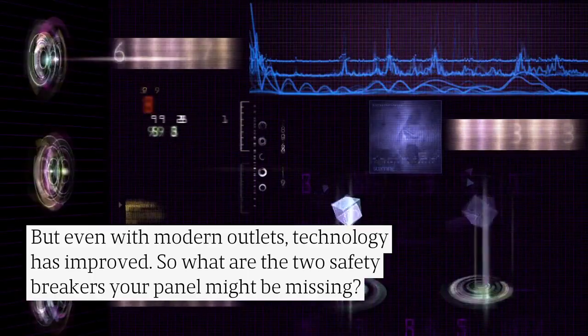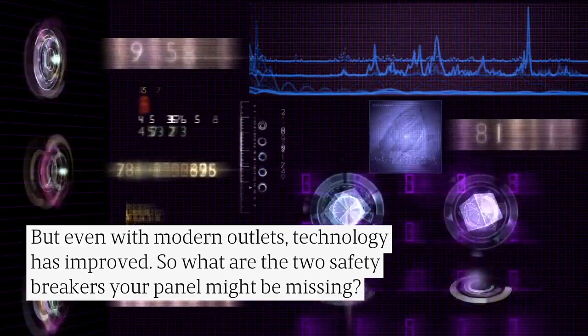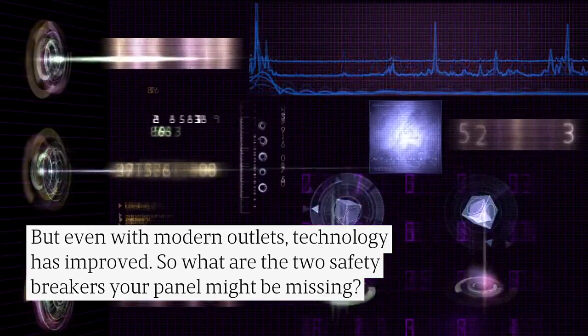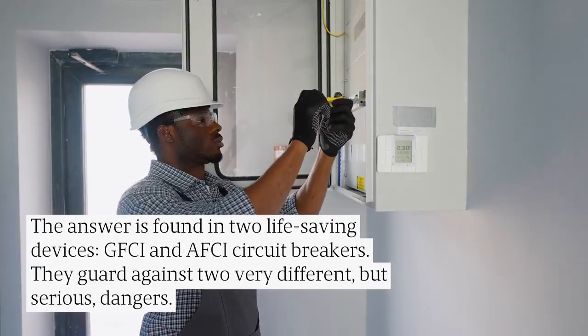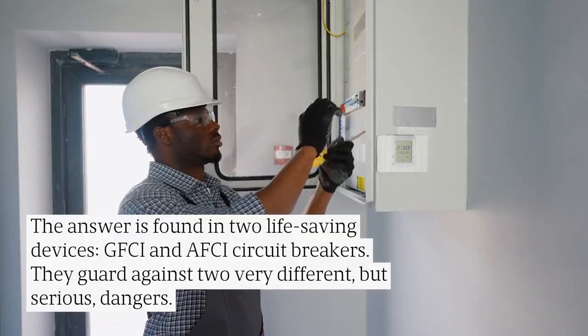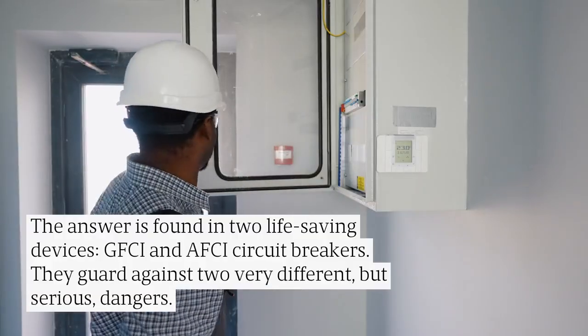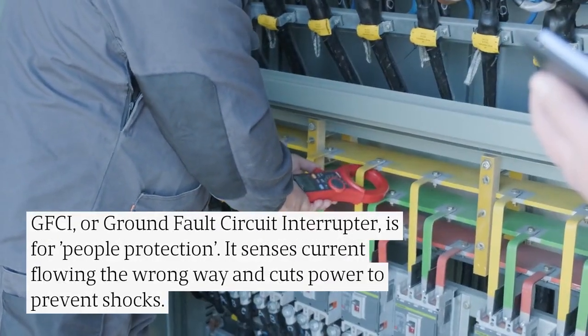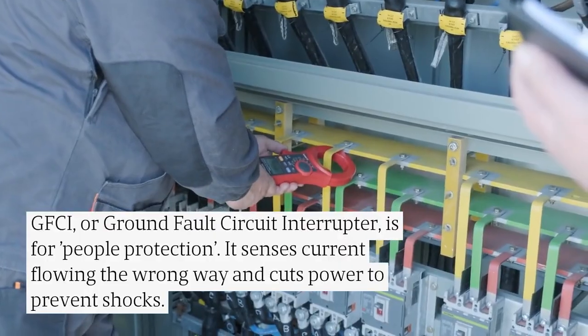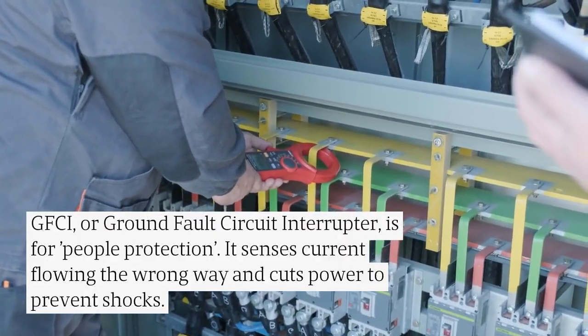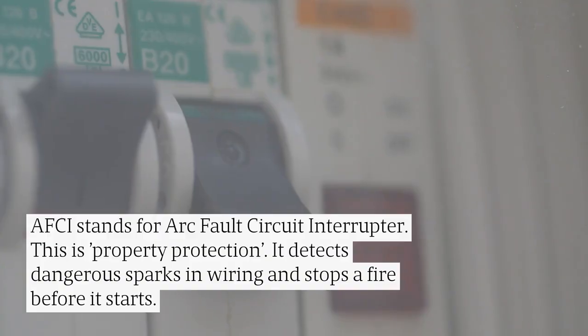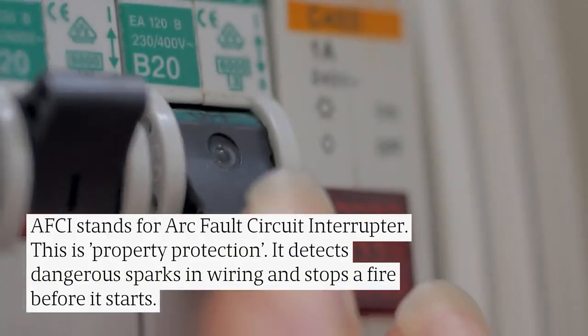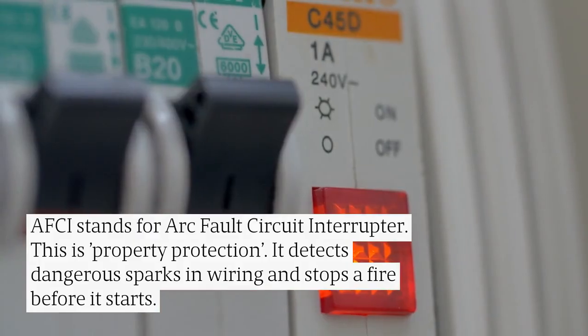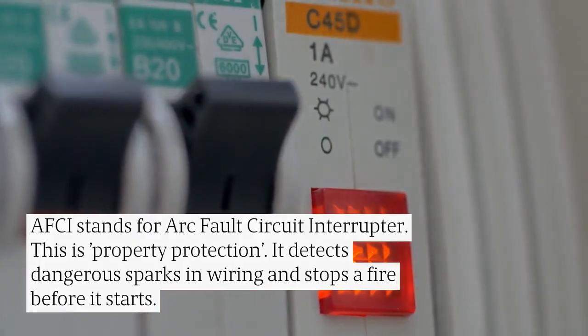But even with modern outlets, technology has improved. So what are the two safety breakers your panel might be missing? The answer is found in two life-saving devices: GFCI and AFCI circuit breakers. They guard against two very different but serious dangers. GFCI, or ground fault circuit interrupter, is for people protection. It senses current flowing the wrong way and cuts power to prevent shocks. AFCI stands for Arc Fault Circuit Interrupter. This is property protection. It detects dangerous sparks in wiring and stops a fire before it starts.